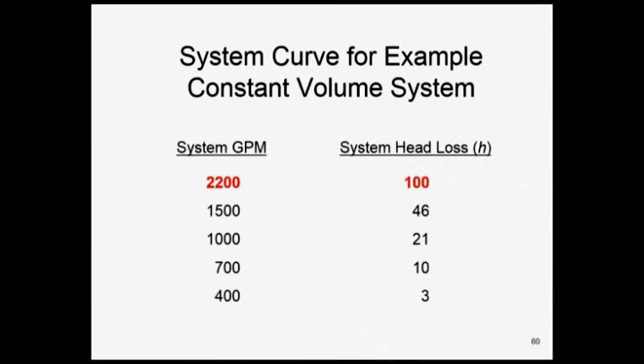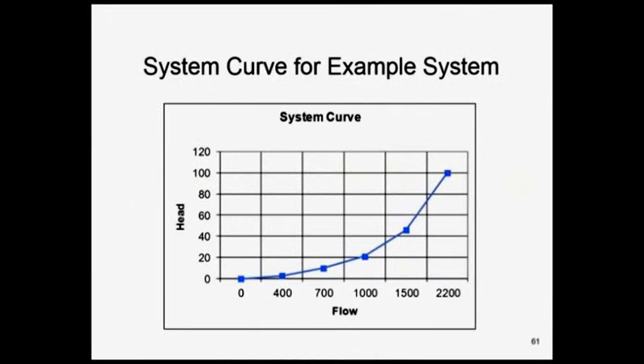I can tell you the pressure drop at any other flow rate. And now I take this and I come up and I plot a system curve. So there's my system curve. That's unique to your job. Valves wide open and fixed, unique to your particular situation, your school, your hospital, your pump. That's unique to you. But it shows you the pressure drop at any other flow rate.